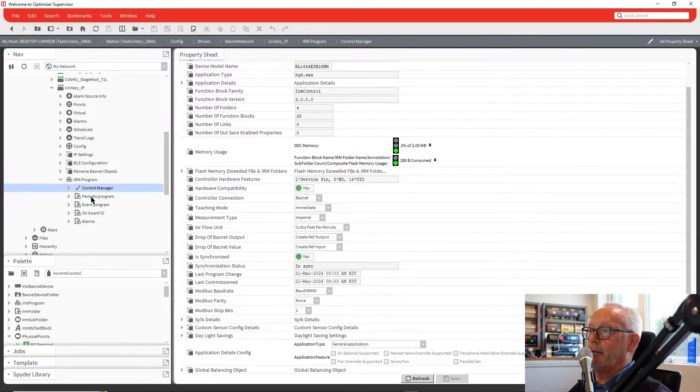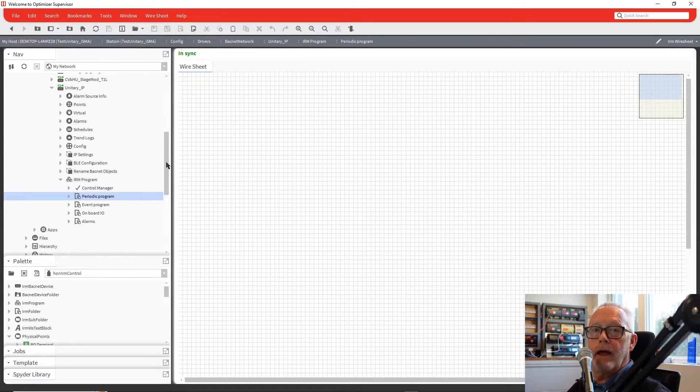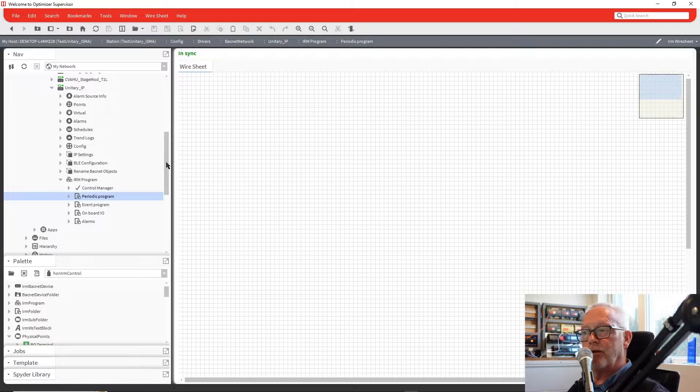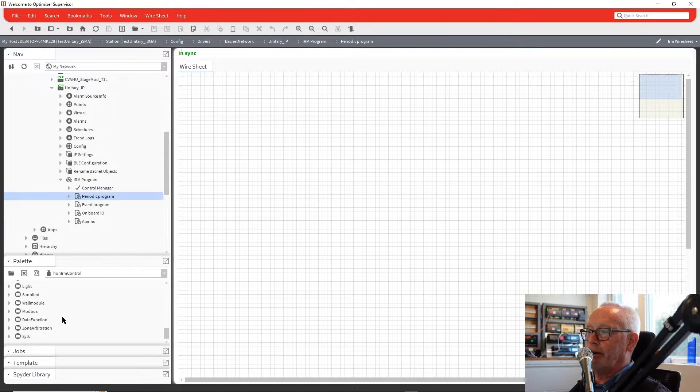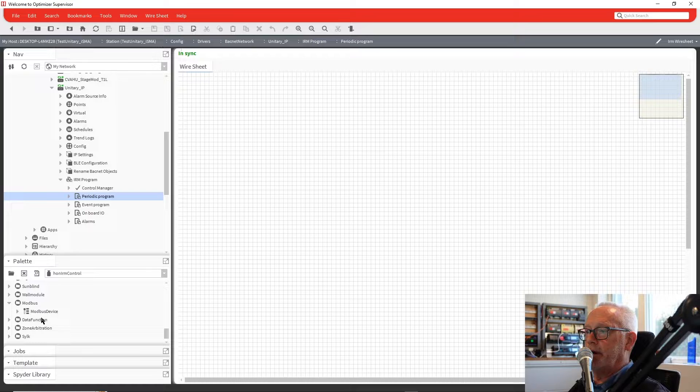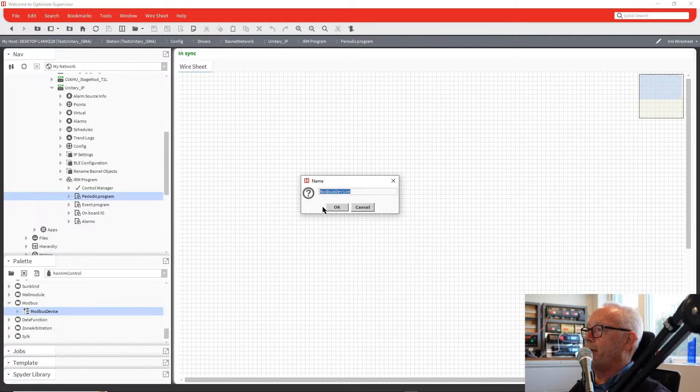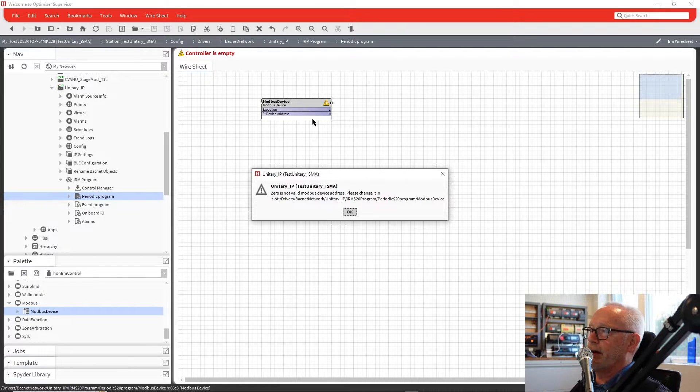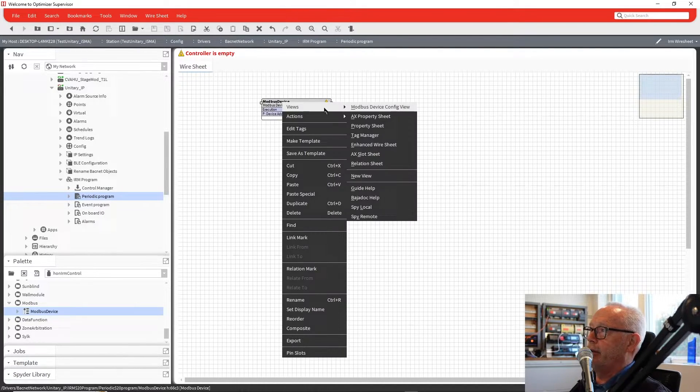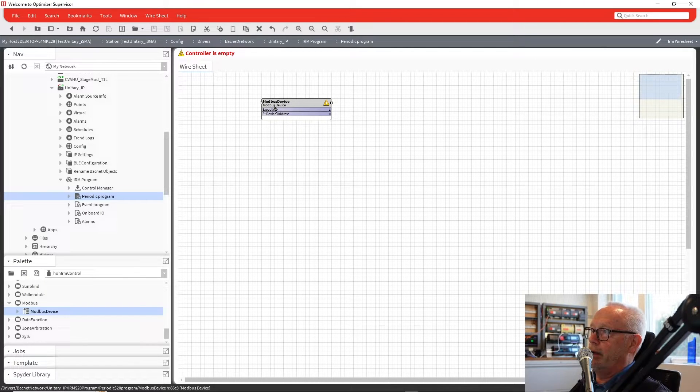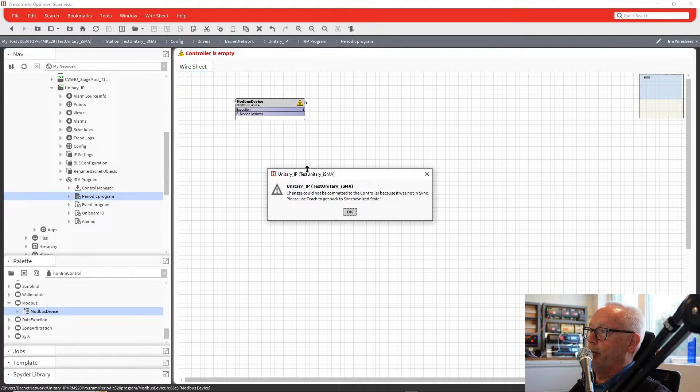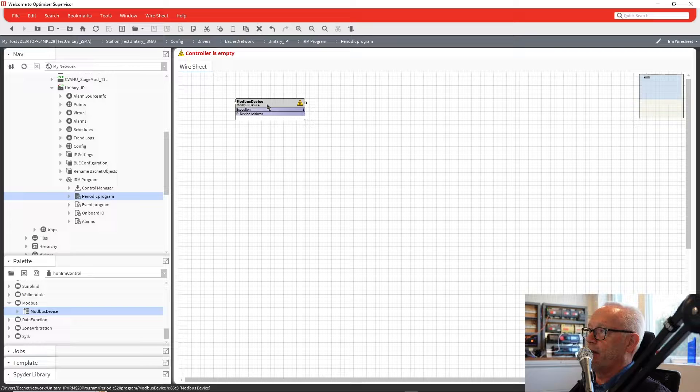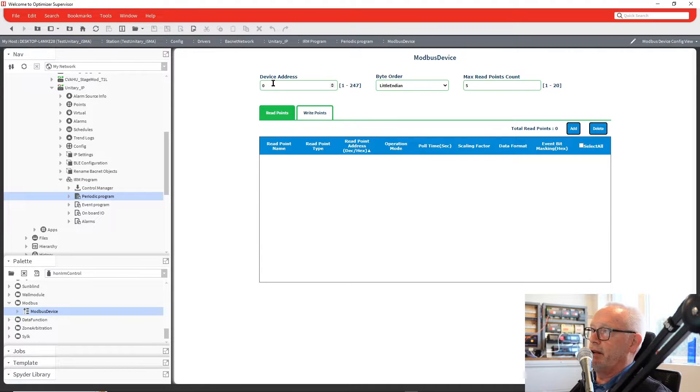I can go to my periodic program folder, and we're going to add that device from the palette. We go down to the bottom of the Honeywell IRM control palette, select Modbus device, and drop that on the screen. Right away, it comes up and says it's a zero address, you need to change that. If we double-click on this device, it will bring up the configuration view for Modbus.